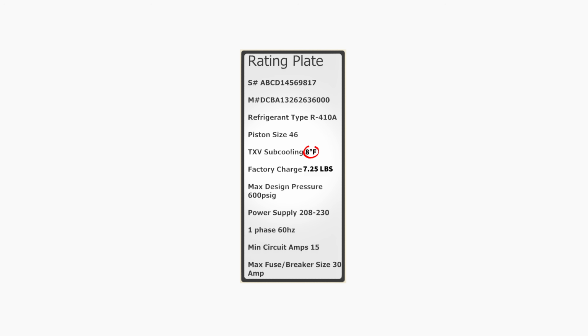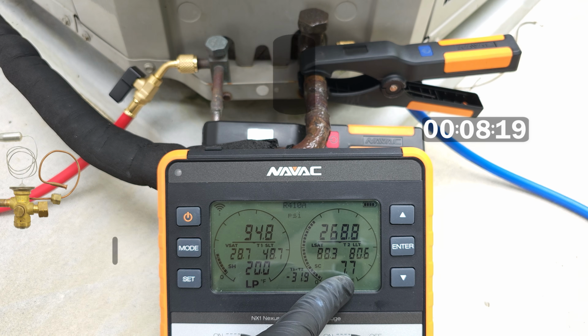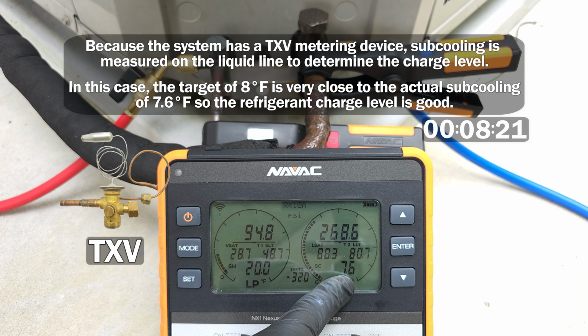Up on the rating plate, this unit is calling for 8 degrees of subcooling, so we're very close in the subcooling, which means that the refrigerant charge is most likely correct because we have a thermostatic expansion valve at that indoor coil.